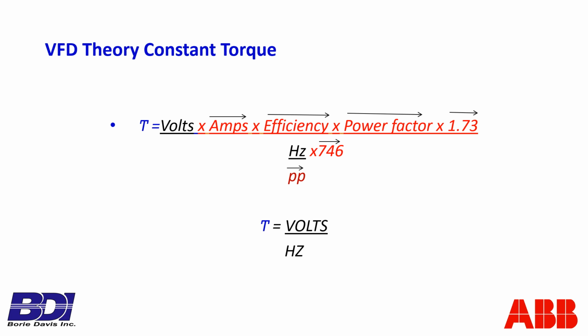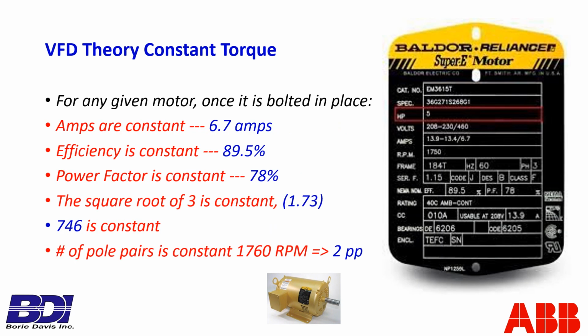Okay? They're not changing. So you wind up with an equation that says torque is equal to volts divided by hertz, voltage divided by frequency. This is where that information comes from. You take a picture of the motor nameplate on startup and you gather this information right off the nameplate. There's the horsepower, 5 horse. There's the 460 volts. Make sure that's what your supply is. The motor's rated 6.7 amps at 460 volts, and it's a 1760 RPM motor. That, I know, means it has 2 pole pairs in it. Okay.